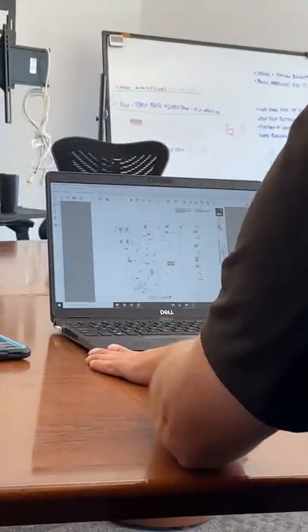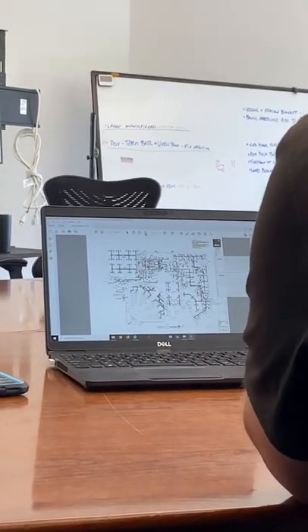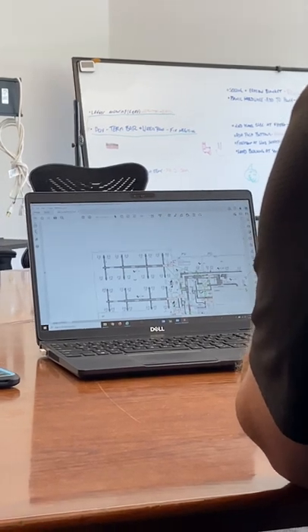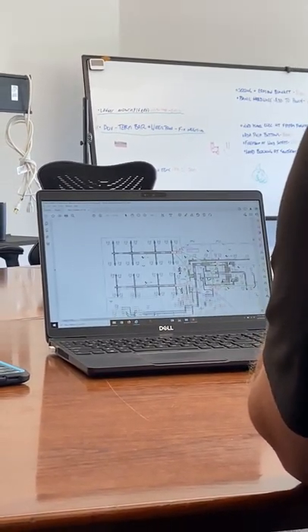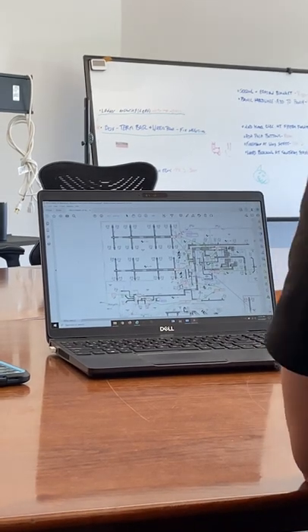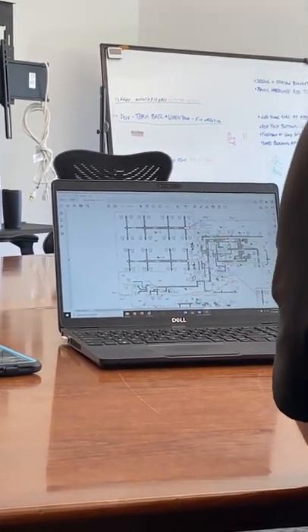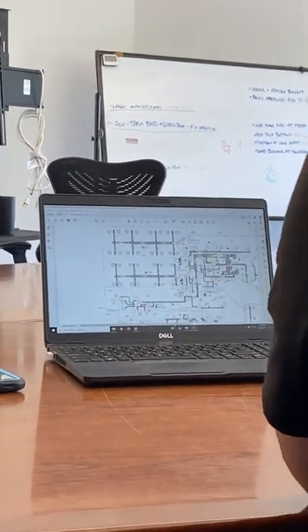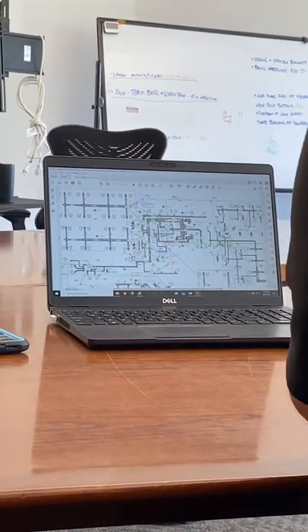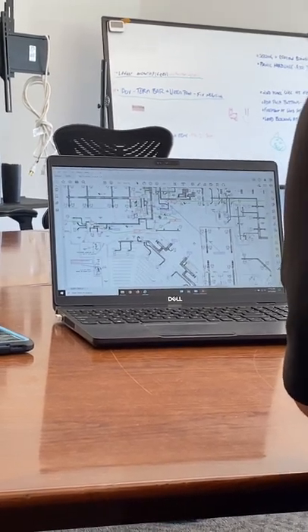Here are the ones we have — to kind of show how the wires go in and stuff like that. I think that'd be handy to just have a quick link to those. Because he may be looking going, what does RTU5 feed? I'm hot on the north side — why? So this is what we got, that's our BACnet cable — that's how everything talks to each other. And we can even color coordinate some of this stuff for the different units if you'd be willing to do that.